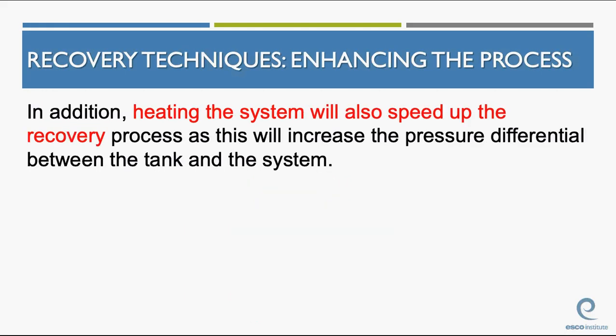In addition, I can add heat to the system itself to speed up the recovery process. In other words, if I heat up the refrigerant in the system, I increase the pressure differential between the tank and the system. The larger that differential is, the faster the refrigerant is going to want to flow into the tank. How would I heat up a system? What's the easiest way for me to heat up a refrigeration system that's installed in somebody's house?